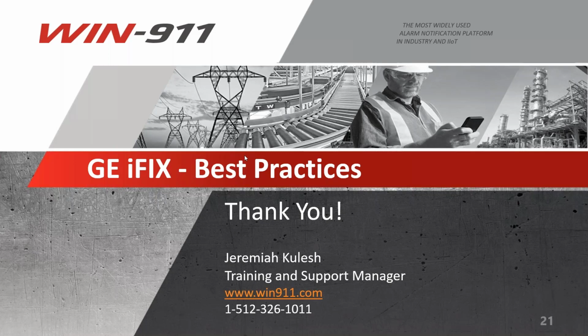All right, next question here. Can WIN-911 Interactive be installed on a computer on the SCADA network with access to the SCADA servers, but with no iFIX software? No, it has to be on a view node or the iFIX server. It has to be one of those two, Dustin. The reason is that you need to call upon that alarm user queue from the local machine where that file is. You can't be going across the network to a different machine to pull that.